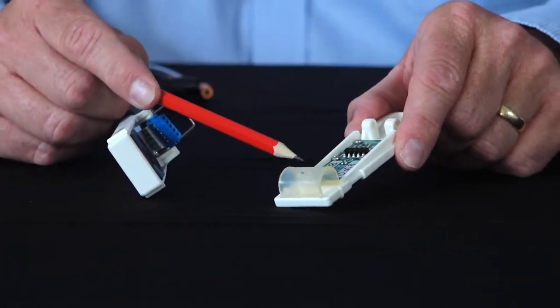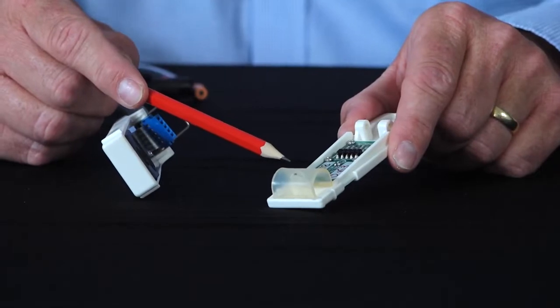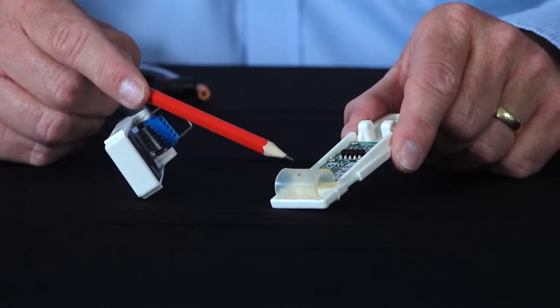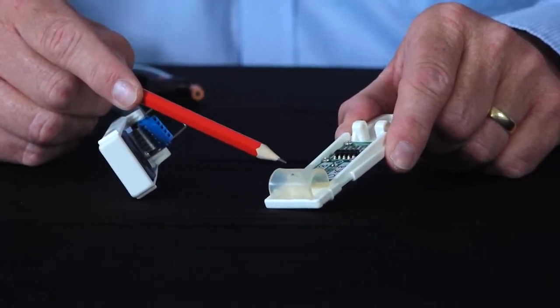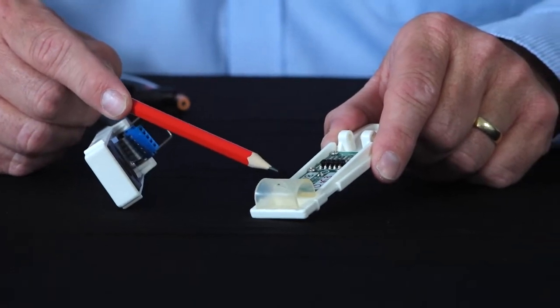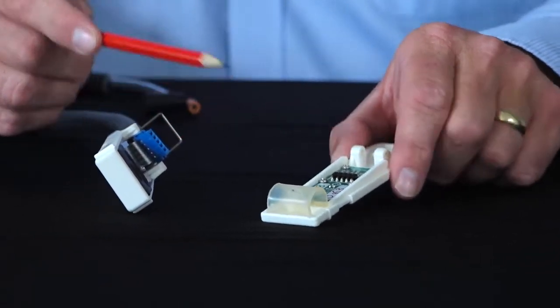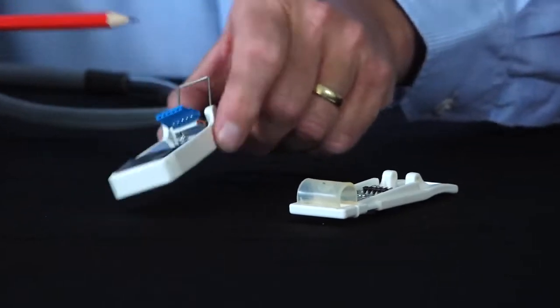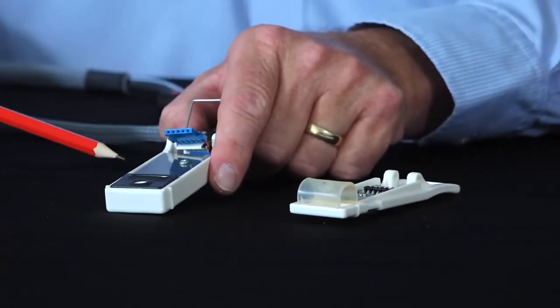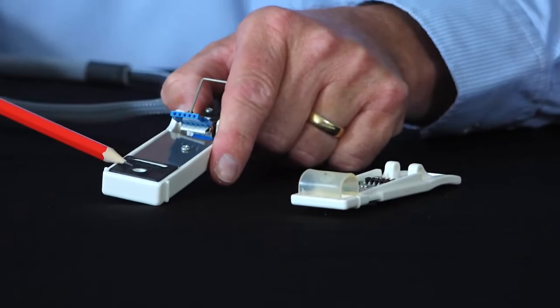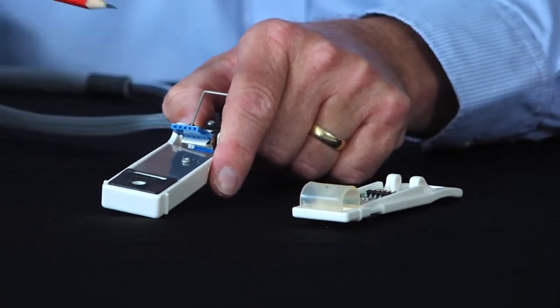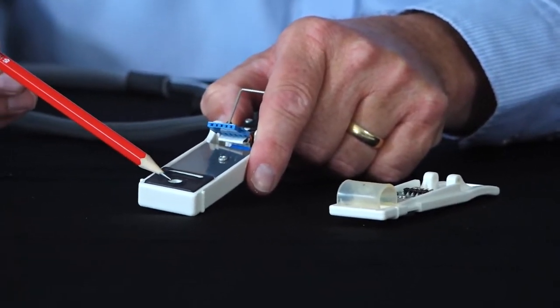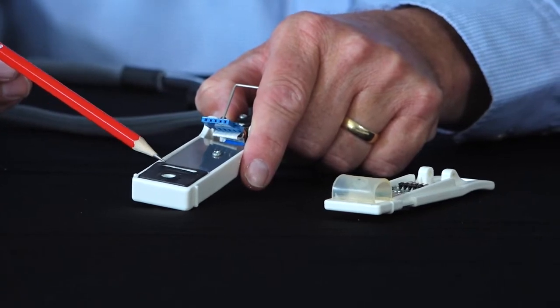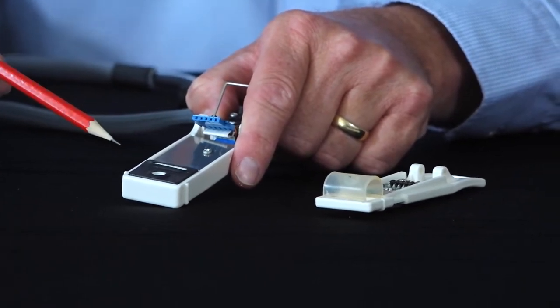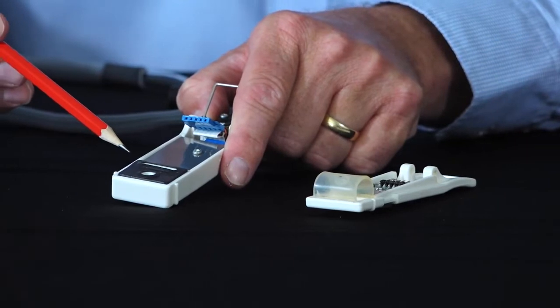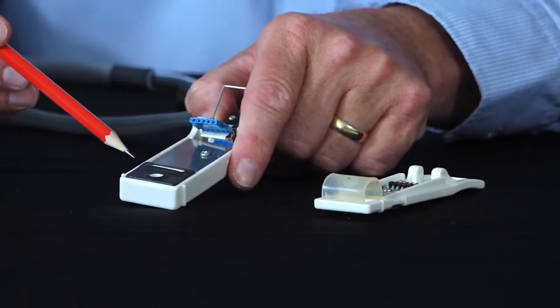Embedded in this rubber is a wire. And this is actually a thermistor, which is measuring the temperature of the leaf. And temperature measurement is very important for being able to get an accurate relative humidity measurement. The bottom half of the clip is where we have our measurement cup, where we're collecting the humidity into the cup. At the very bottom of there's a small square fast response relative humidity sensor, and next to it another thermistor for measuring the cup temperature.